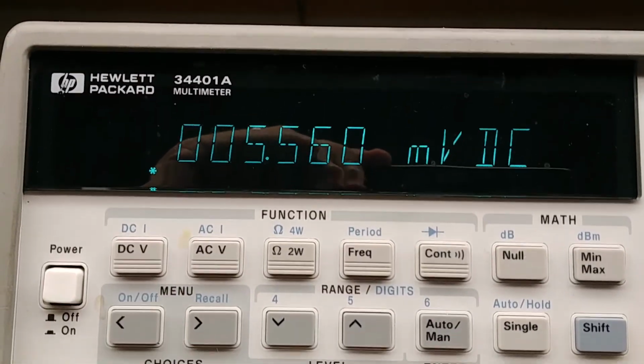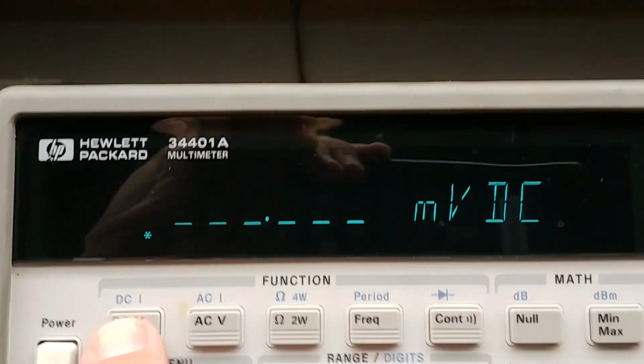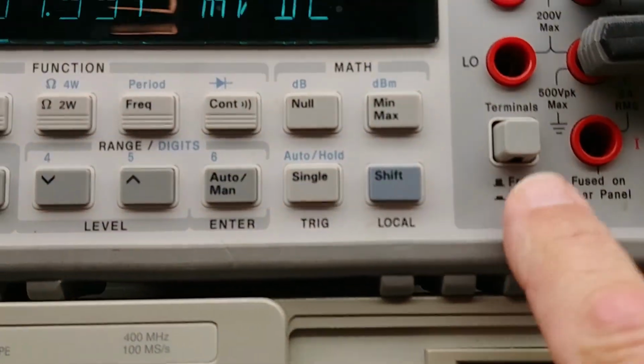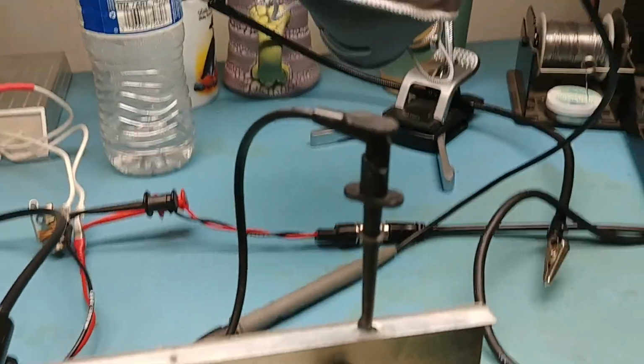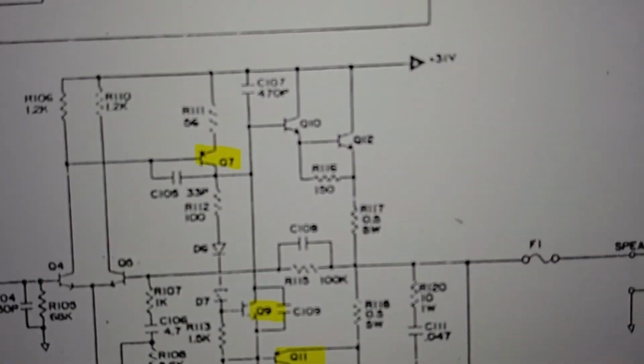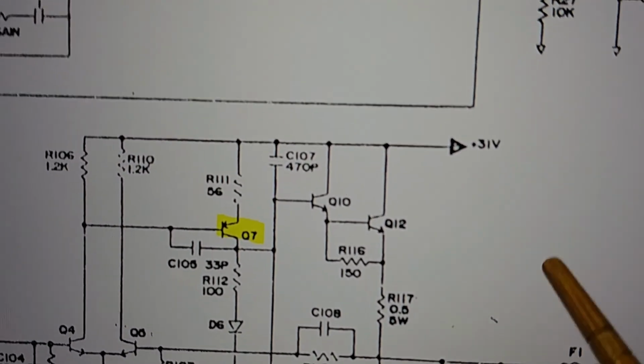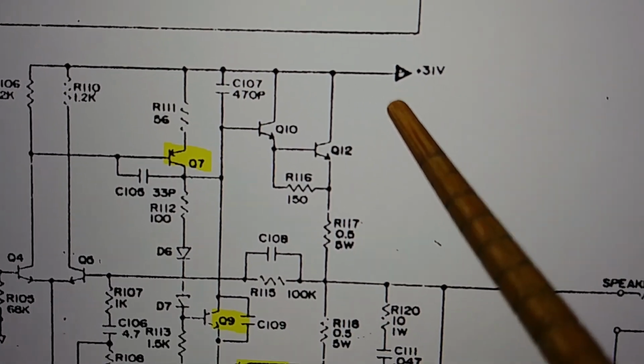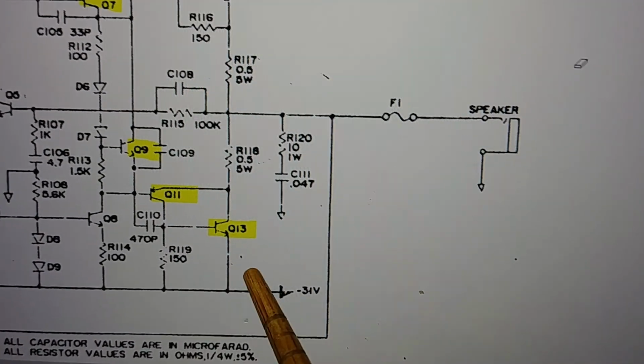So that tells me if I set my voltmeter to DC volts, which it is, I've got my terminals measuring from the front, which I do. I've got this guy grounded. So if I check the collector of Q12, right here, I should measure 31 volts. If I check the emitter of Q13, I should be measuring negative 31 volts. Let's see what happens.